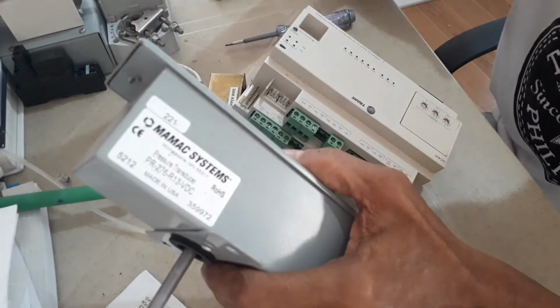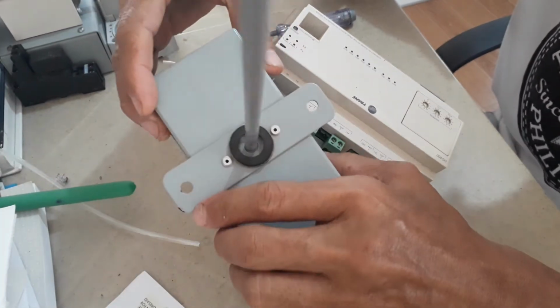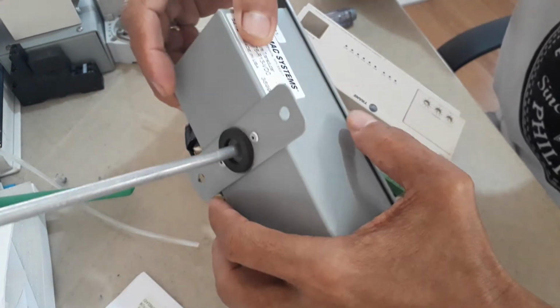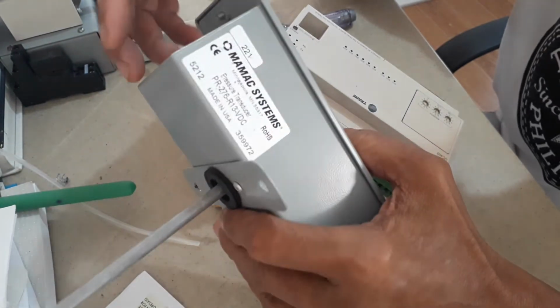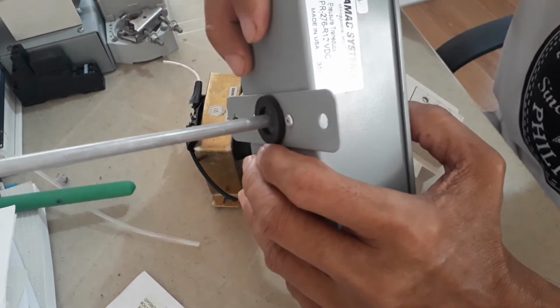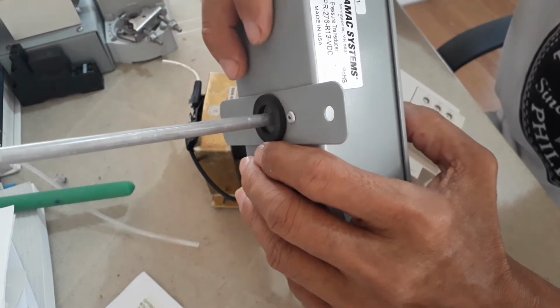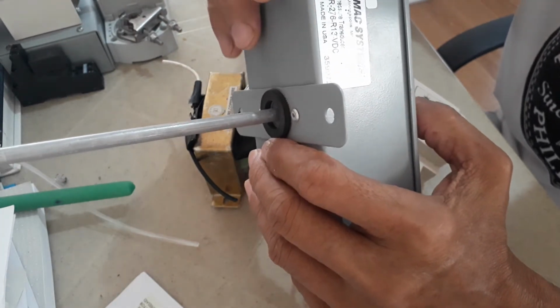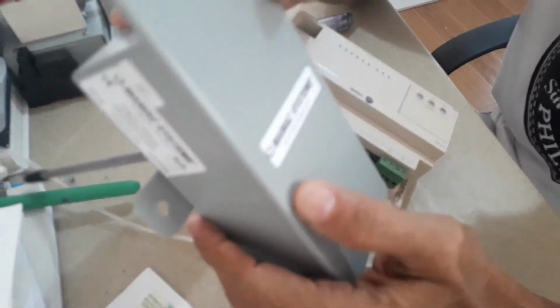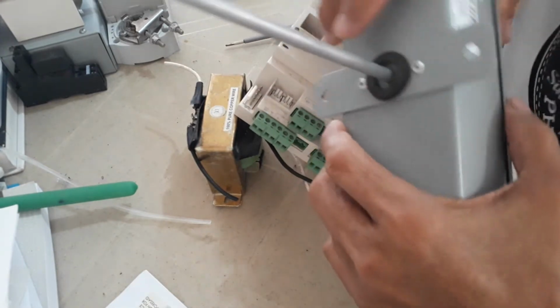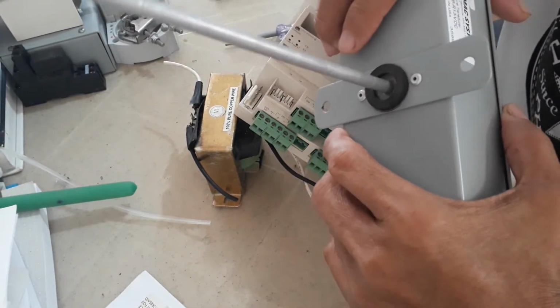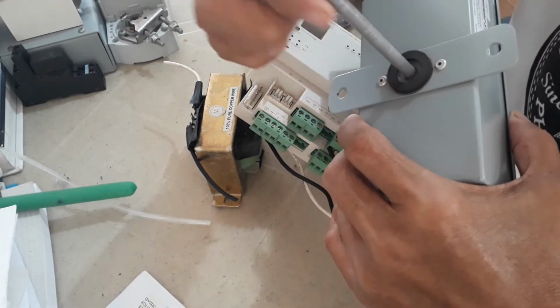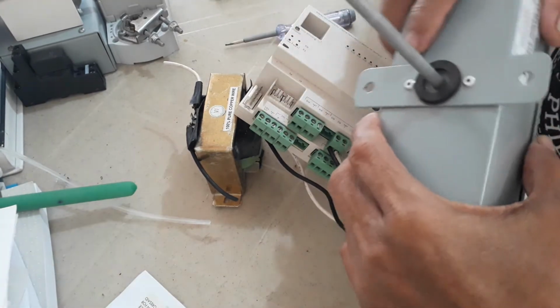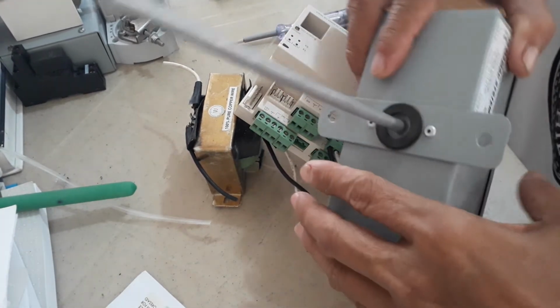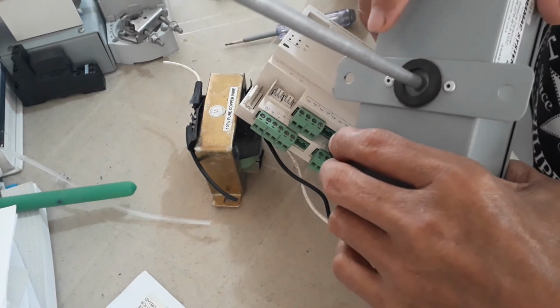Now, what I'm going to show you today is how to wire and provide a power supply for a duct pressure transducer. So, this is a duct pressure transducer, okay? This is a MAMAC system, as you can see here. This is made in USA. Now this is a duct pressure transducer, meaning you have to insert this probe inside the duct of our airstream, okay?